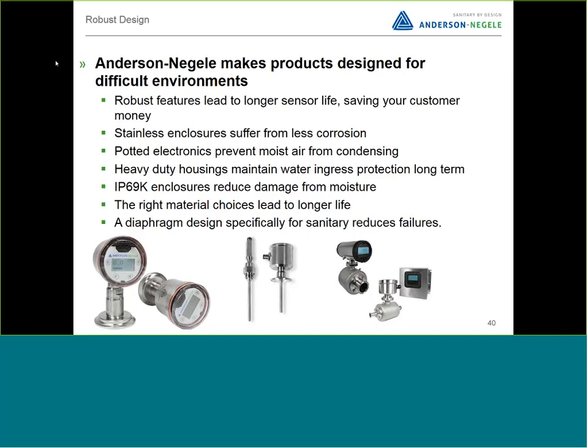The design methodology around the dual O-ring seals and becoming more IP69K focused than NEMA 4X focused has really come on in the last 3 to 4 years. So as we've been releasing new products in roughly the last 4 years, we've been focusing a lot more, and the dual O-ring seal originated in the MPF product, and we've been rolling it into other designs since then.